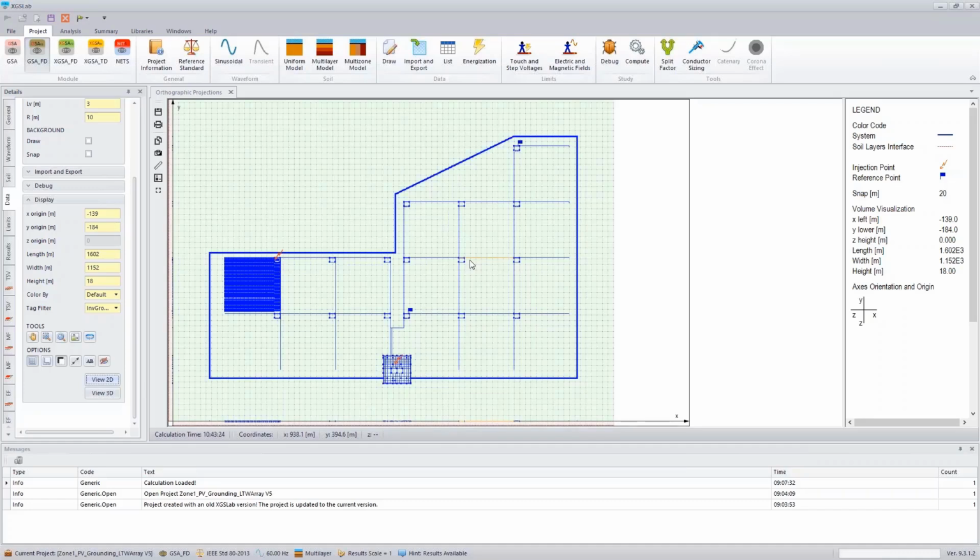So there are different testing outfits that have different processes for validating grounding system design. And I think that's just highly recommended in any sort of engineering process, is to validate the design and perform engineering measurements after the construction to verify that, first off, it was constructed to design, and that the data going in provides accurate data going out.